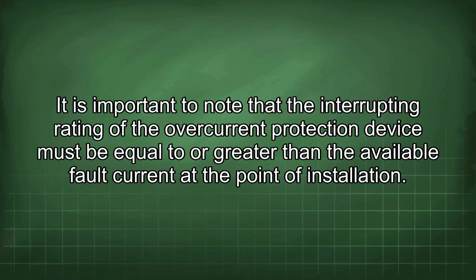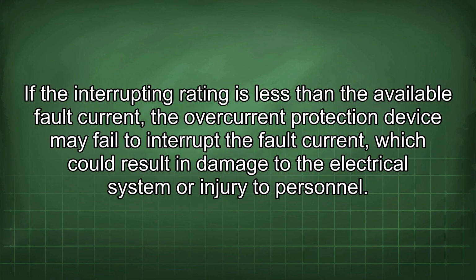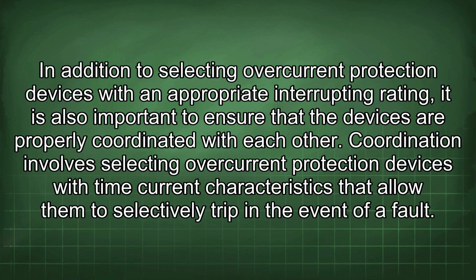It is important to note that the interrupting rating of the overcurrent protection device must be equal to or greater than the available fault current at the point of installation. If the interrupting rating is less than the available fault current, the overcurrent protection device may fail to interrupt the fault current, which could result in damage to the electrical system or injury to personnel. In addition to selecting overcurrent protection devices with an appropriate interrupting rating, it is also important to ensure that the devices are properly coordinated with each other.